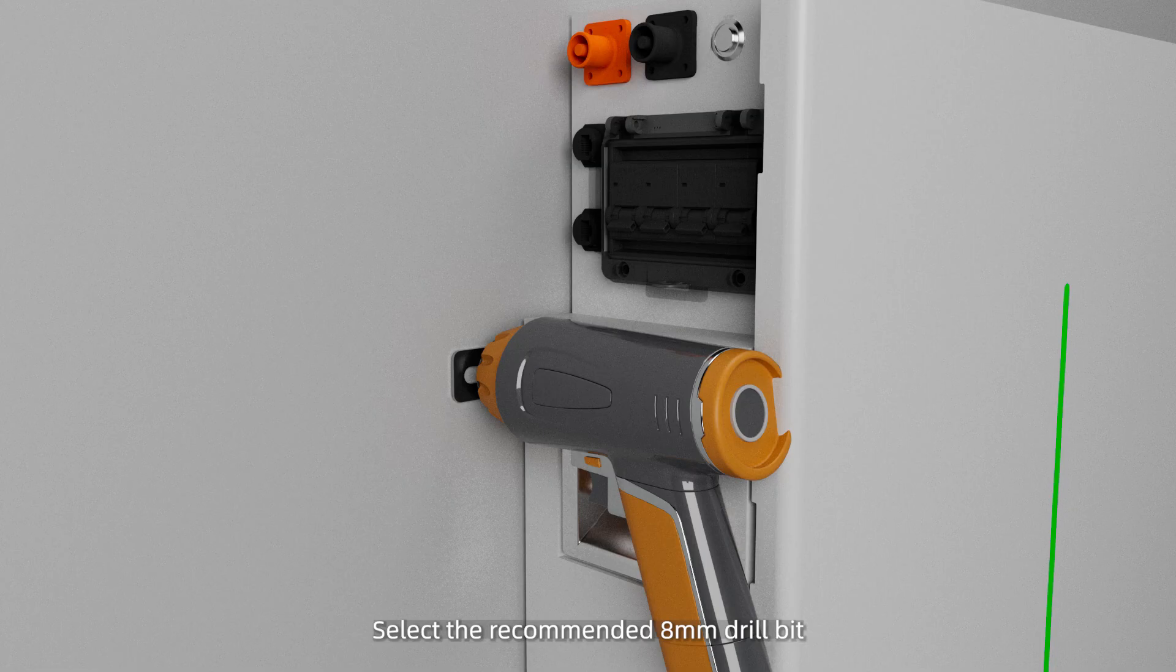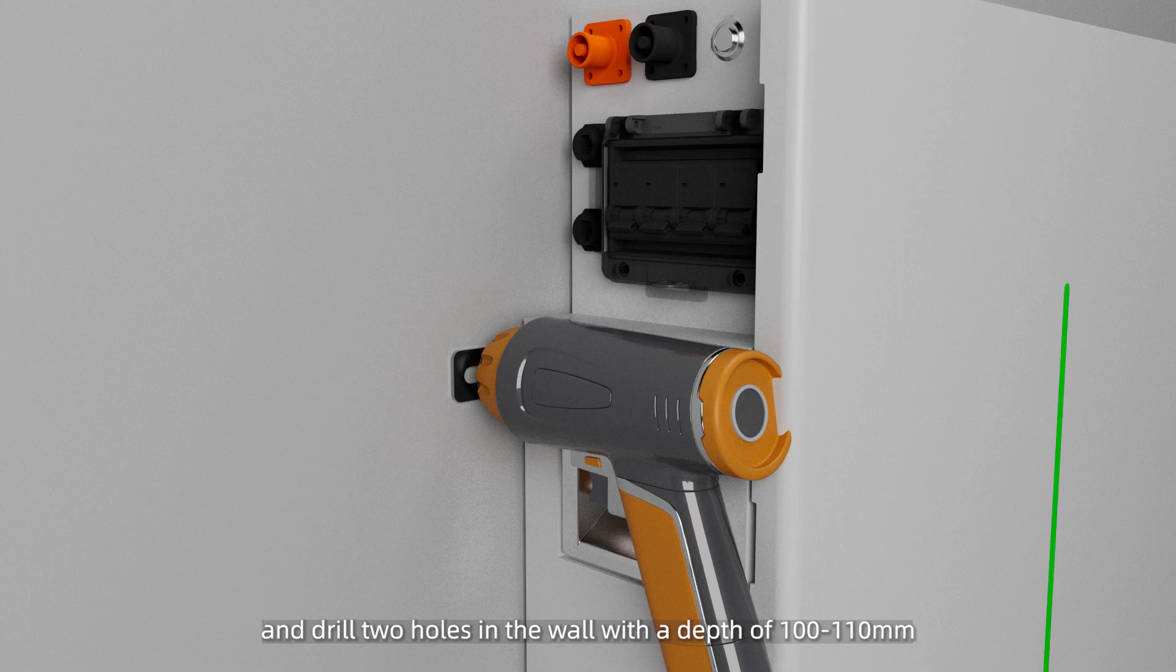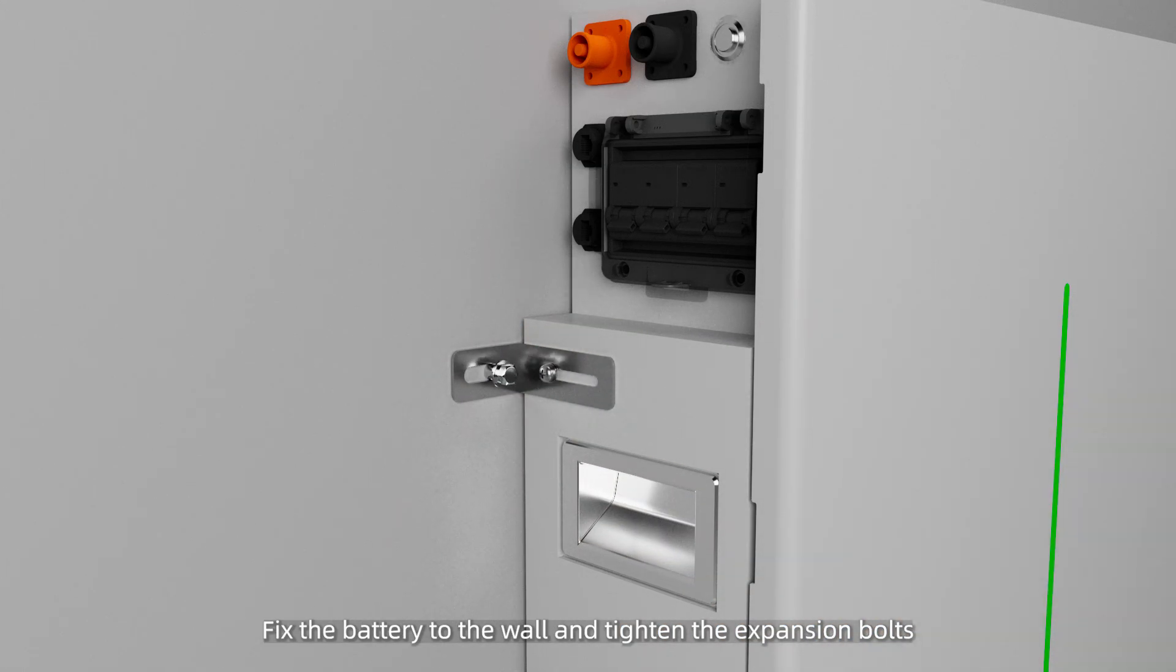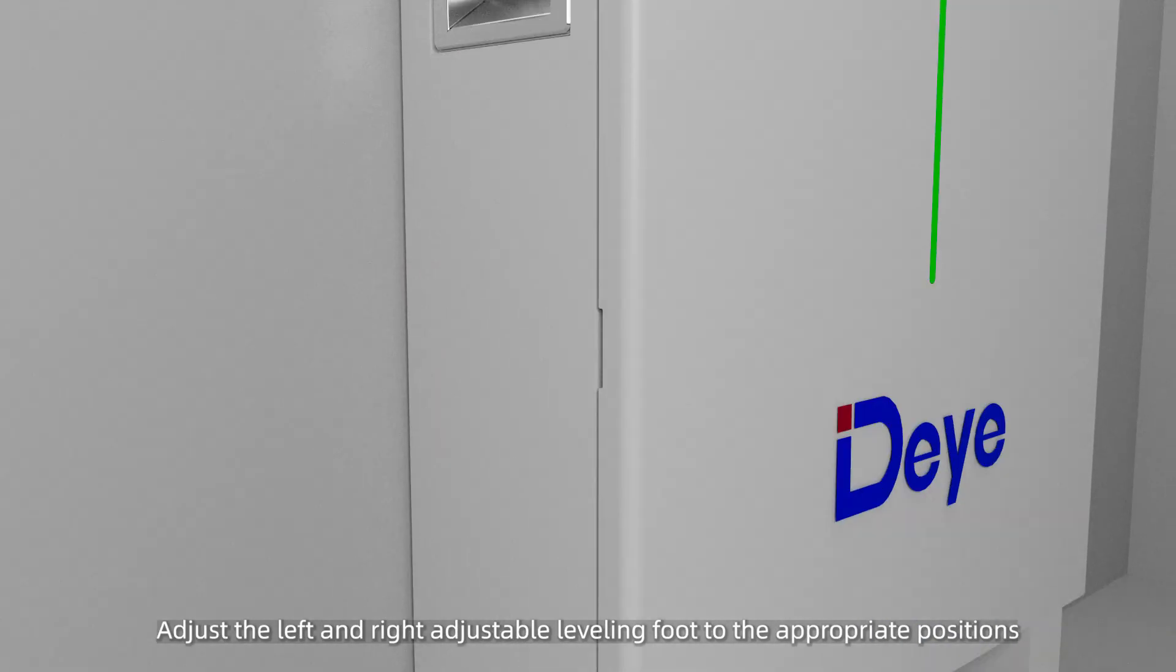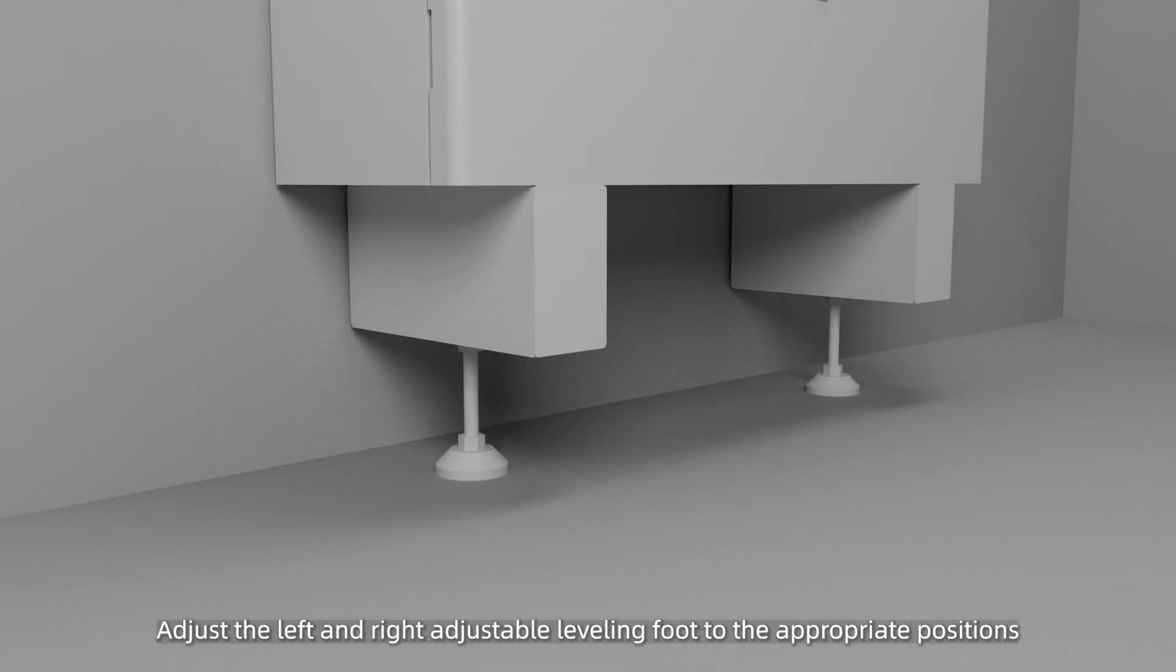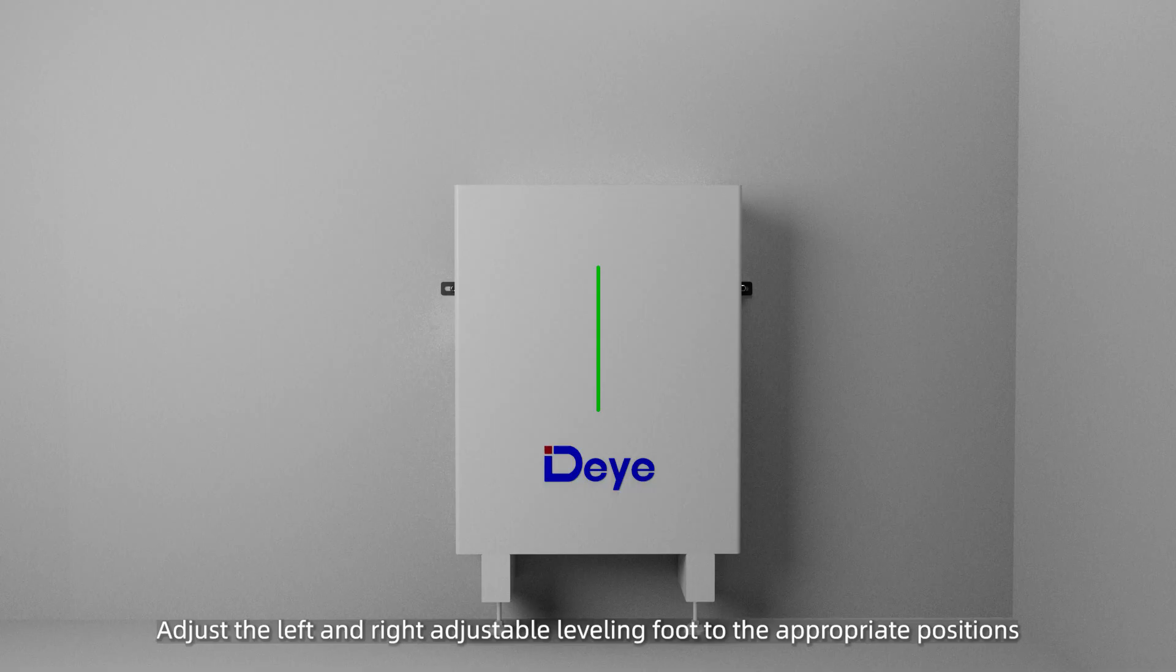Select the recommended 8mm drill bit and drill two holes in the wall with a depth of 100 to 110mm. Fix the battery to the wall and tighten the expansion bolts. Adjust the left and right adjustable leveling foot to the appropriate positions to make the battery perpendicular to the ground.